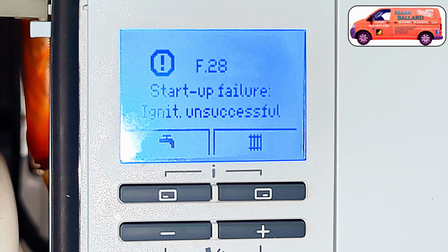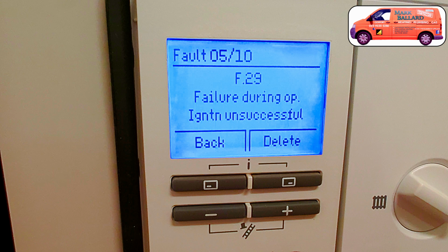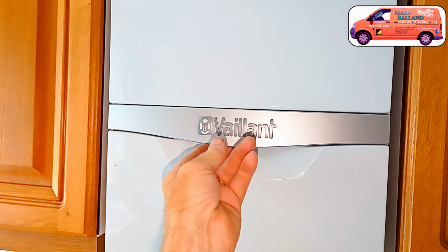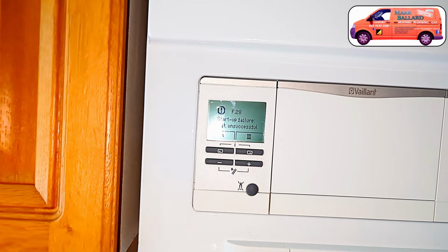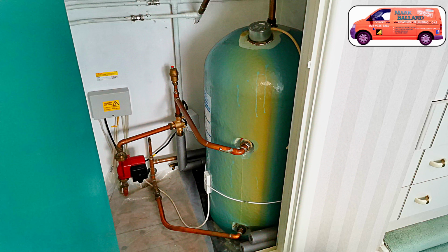Hello! Has your Vaillant boiler stopped working and it has F28 or F29 on the display? This video in particular is for the Vaillant Ecotec Plus 400 series boilers. That's a heat-only boiler where you may have that large hot water tank. But the fault causing the problem, which I'm going to show you how to fix, can apply to all modern boilers. So do stick around because this fault could apply to your boiler.